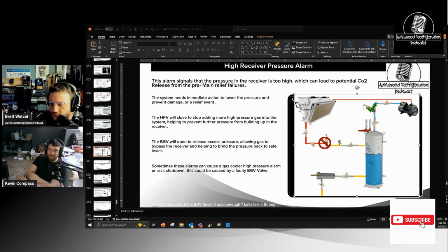But just about every time you end up with low receiver pressure issues, it's generally a BGV issue, not an HPV issue. So the HPV gets blamed more than the BGV when it's the BGV. And then same thing with cycling issues. Hill Phoenix likes to tie their shutdown signals into these tiny little relays, and it kills the 326A or the iPro enable. Those relays go bad all the time, and they do it intermittently.